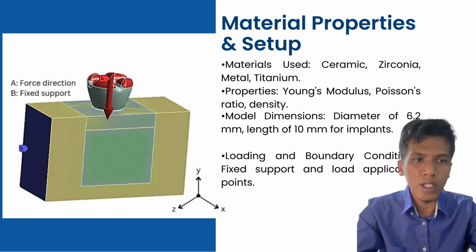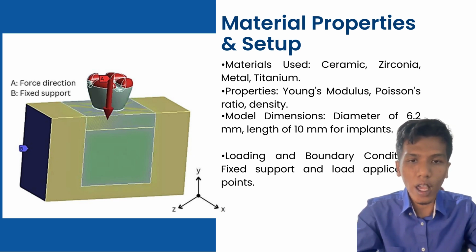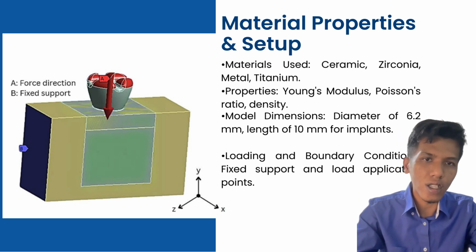For the model dimensions, basically we have a diameter of 6.2 millimeters, and the length of the implant is about 10 millimeters. For the loading condition, you may refer to the figure shown here: A is for the force direction and B for the...